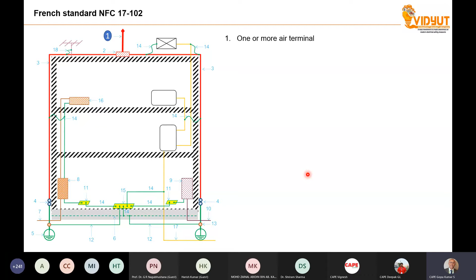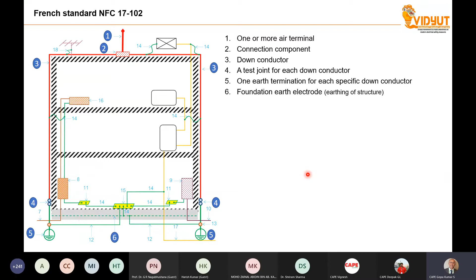It consists of one or more air terminals. This air terminal is the ESE rod, connecting components, and down conductors. Remember, there are two down conductors, whereas in India we always talk about one down conductor. Then test joints, earth electrodes, and the foundation earth electrode. Foundation earth, in the sense that the earth electrode is connected back to the foundation of this particular building. Then you have the electric power cables coming inside, the electric power distribution board, the telecommunication power distribution board, and one or more equipotential bonding bars.